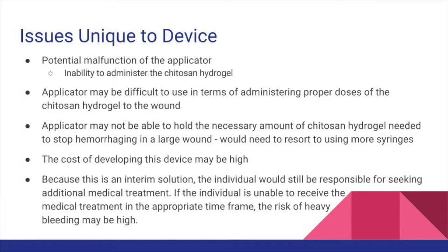Issues unique to the device. One issue is the potential malfunction of the applicator. This would lead to an inability to administer the chitosan hydrogel. The applicator may not be able to hold the necessary amount of chitosan hydrogel needed to stop hemorrhaging in a large wound. At this point, we may need to resort to using more syringes.